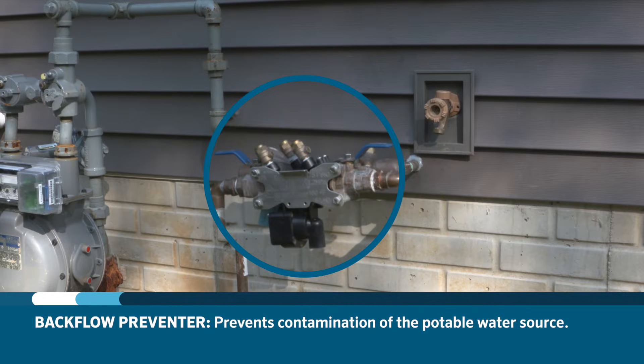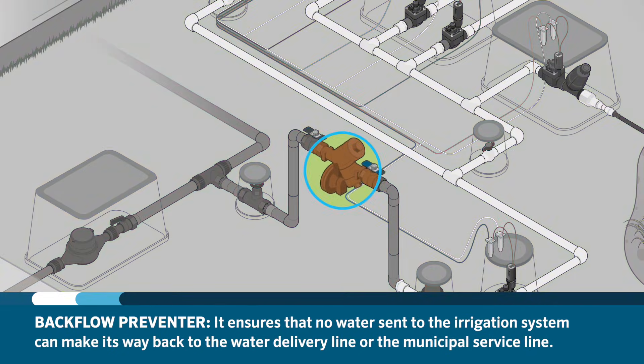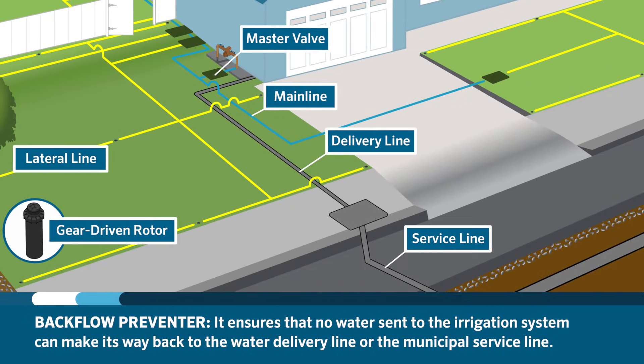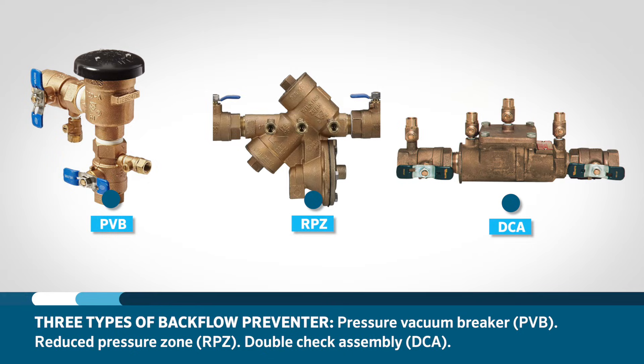Most cities require the use of a device known as a backflow preventer to prevent contamination of the potable water source by ensuring that no water directed to the irrigation system can make its way back to the delivery line or municipal service line. The three most commonly used are a pressure vacuum breaker or PVB, a reduced pressure zone or RPZ, and a double check assembly or DCA. After water passes through the backflow prevention device, internal check valves prevent water from flowing in the opposite direction. Check your local code to determine which backflow prevention device is required for your system.